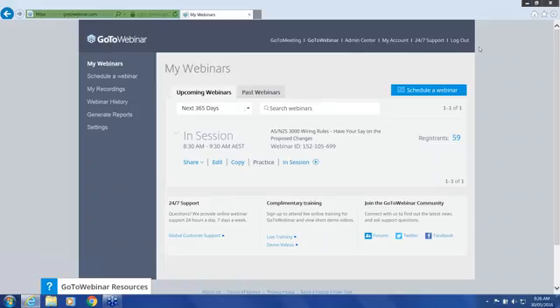Swimming pools: there's been a rewrite of Amendment 2 regarding the common bonding connection point. To clarify, it's required where the pool structure is conductive - unless the pool structure is absolutely non-conductive, you'll need this bonding point, and the bonding point will be earthed. Tying this in with fence structures and similar, there's been some modification to add sizing relaxations.